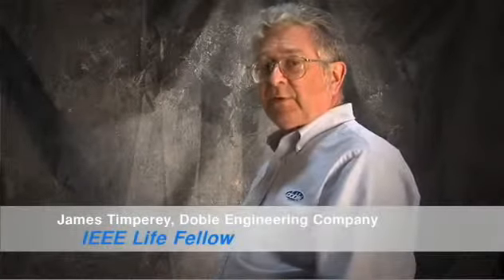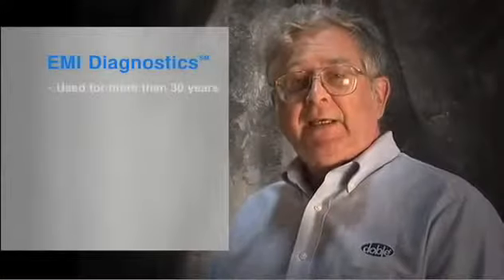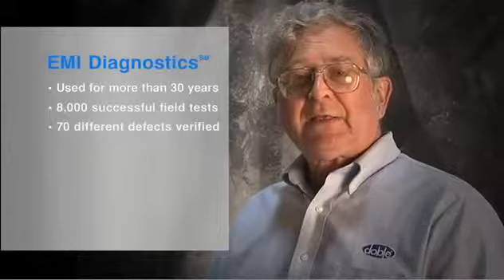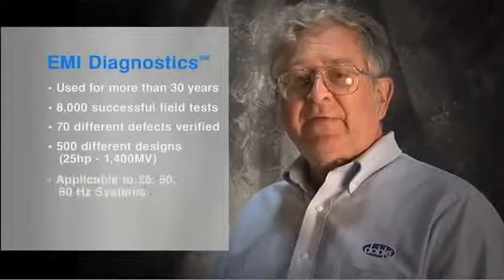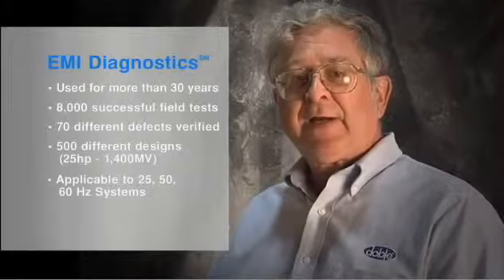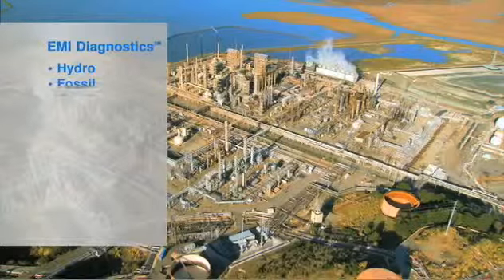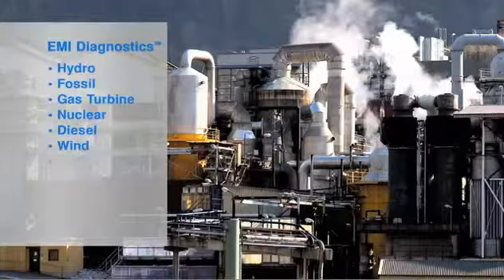Electrical generators, transformers, cables, and switchgear are by design extremely reliable. The biggest problem is these days most of the fleet is at or already exceeded its design service life. Since 1980, EMI Diagnostics has been applied over 8,000 times. To date, over 70 different types of defects and conditions have been identified. The technology has been used at hydroelectric plants, fossil plants, steam turbine plants, refineries, petrochemical sites, and it has been very useful for maintenance people to focus their limited resources during outages and turnarounds only on the equipment that needs attention.